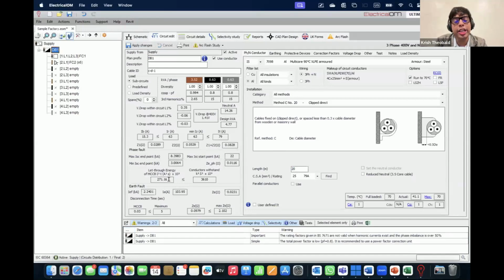Accordingly, it will say this is the fault current, this is the amount of electrical energy the conductors can withstand, earth fault current is this much, current causing operation of the electric device required is this much, this is the earth fault loop impedance, and this is the time it will disconnect. So all that data is calculated based on source characteristics and the length of the conductors to the point of fault, to the extreme point. That is how it calculates.